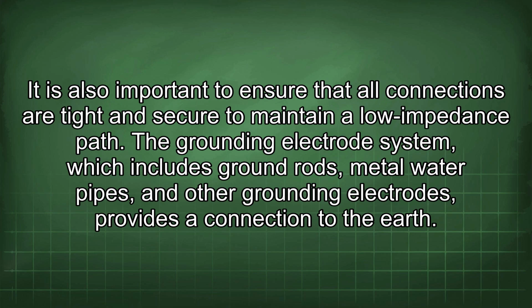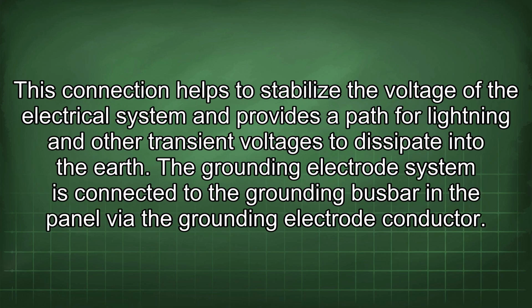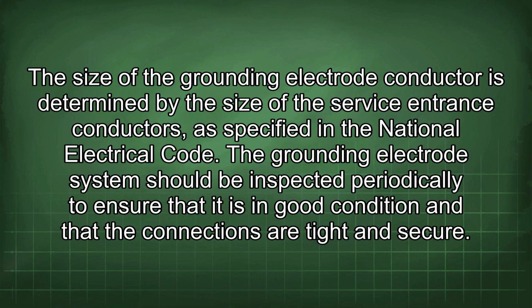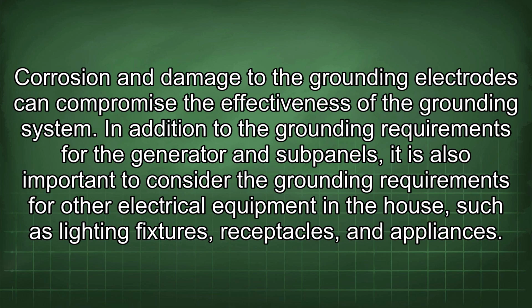The grounding electrode system, which includes ground rods, metal water pipes, and other grounding electrodes, provides a connection to the earth. This connection helps to stabilize the voltage of the electrical system and provides a path for lightning and other transient voltages to dissipate into the earth. The grounding electrode system is connected to the grounding busbar in the panel via the grounding electrode conductor. The size of the grounding electrode conductor is determined by the size of the service entrance conductors, as specified in the National Electrical Code. The grounding electrode system should be inspected periodically to ensure that it is in good condition and that the connections are tight and secure. Corrosion and damage to the grounding electrodes can compromise the effectiveness of the grounding system.